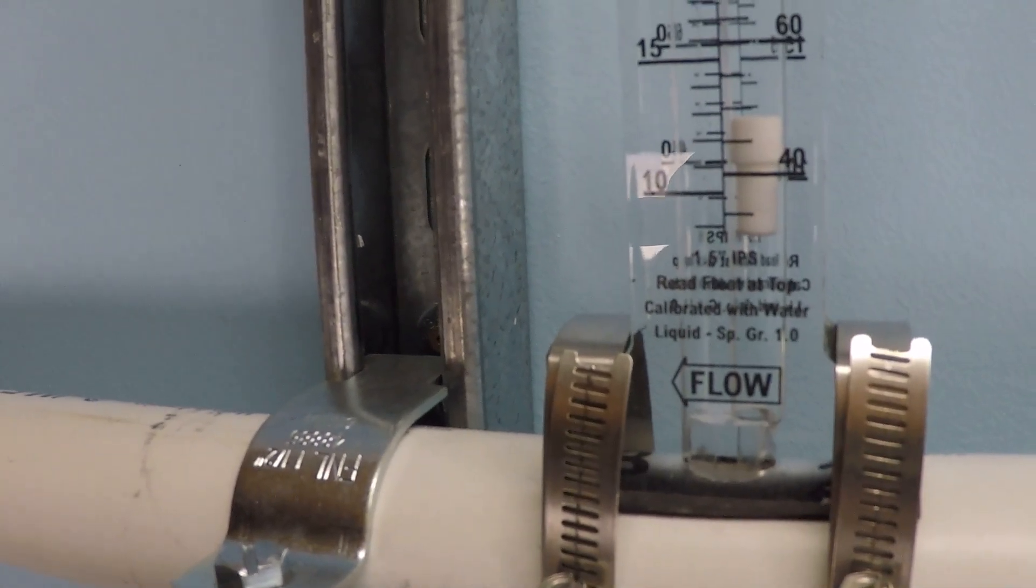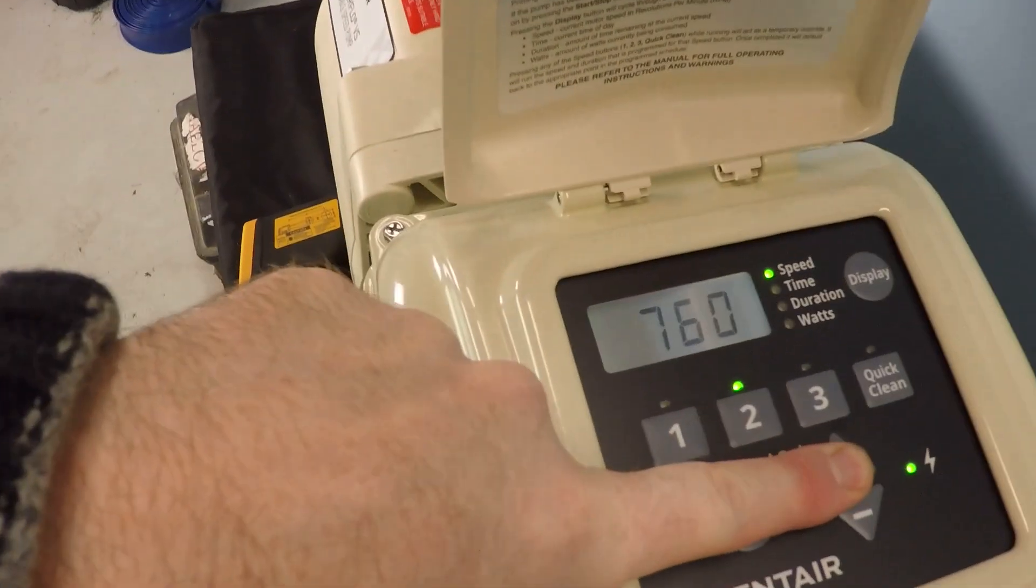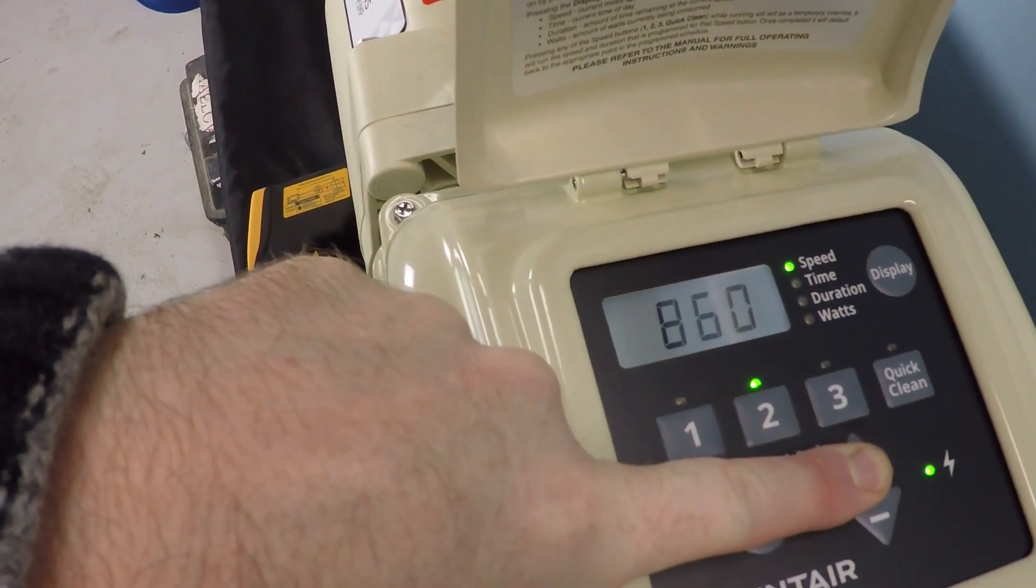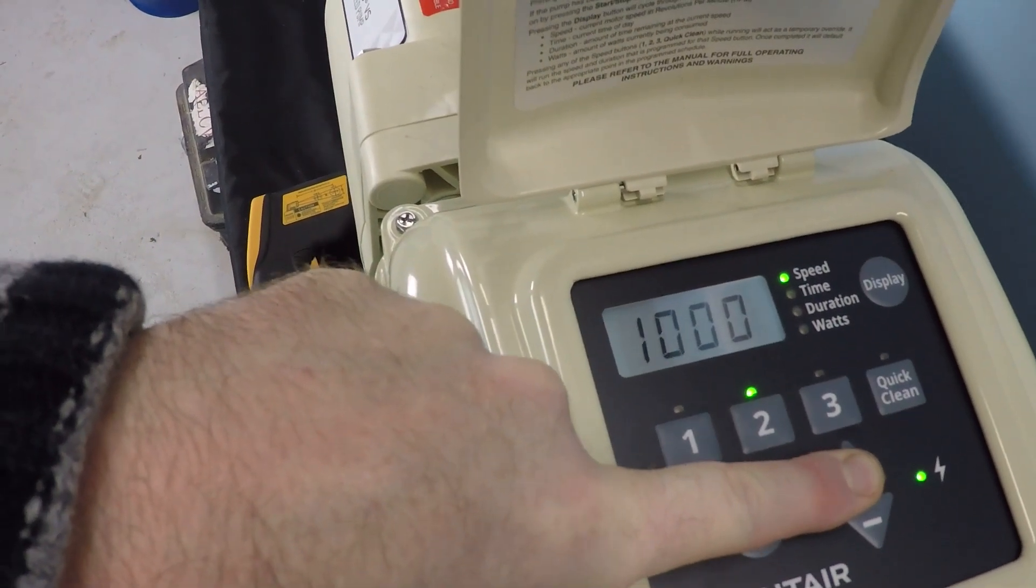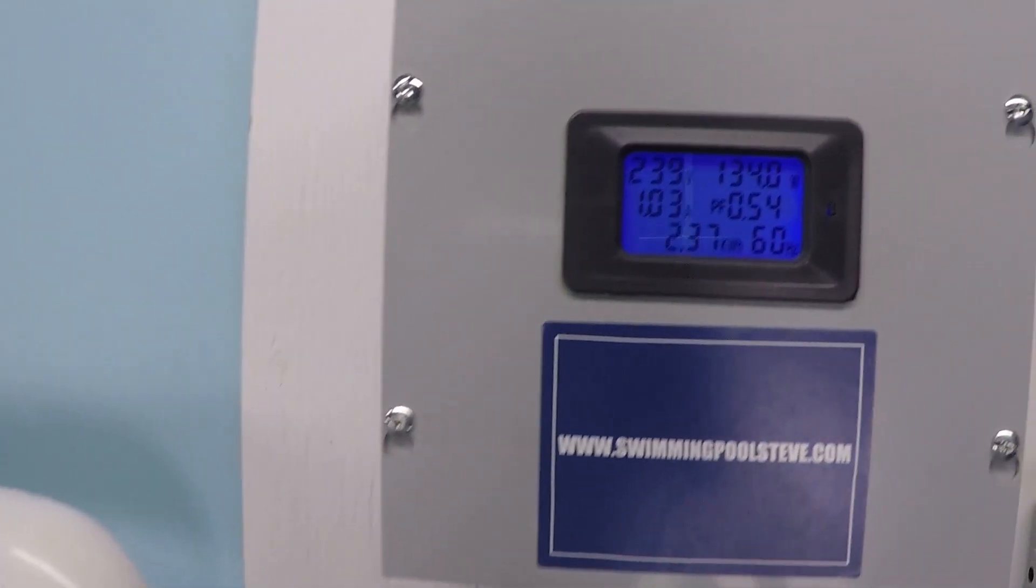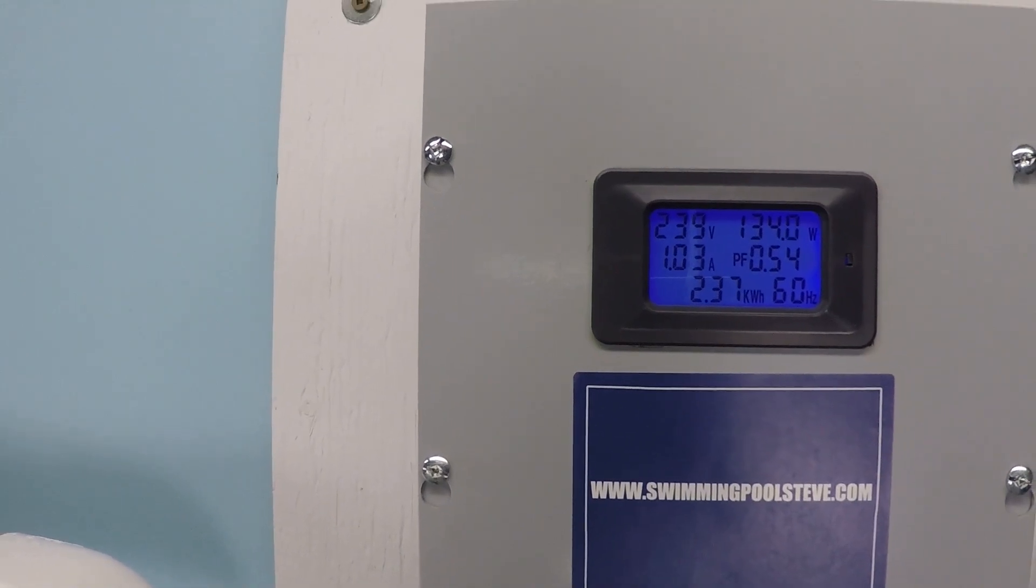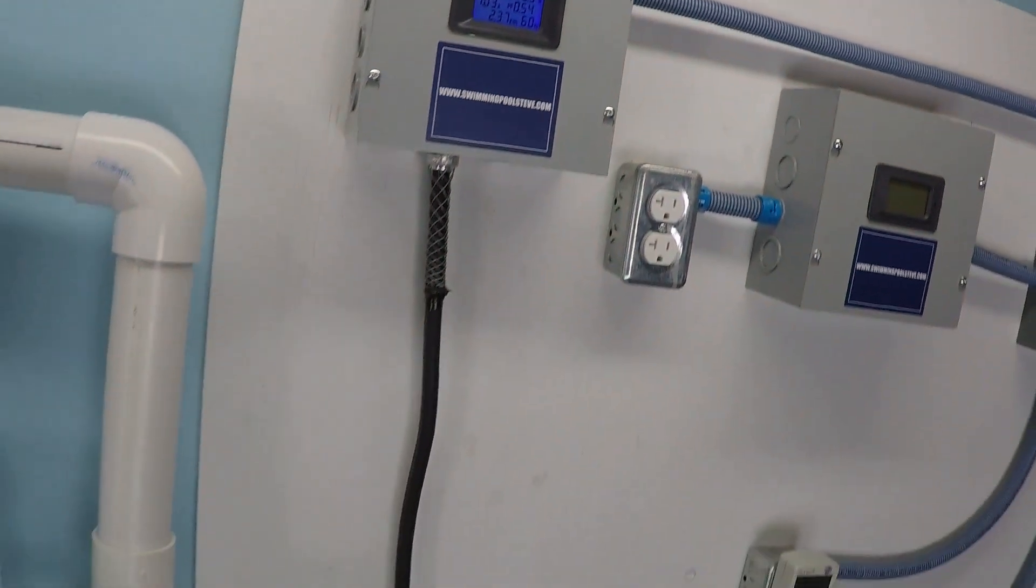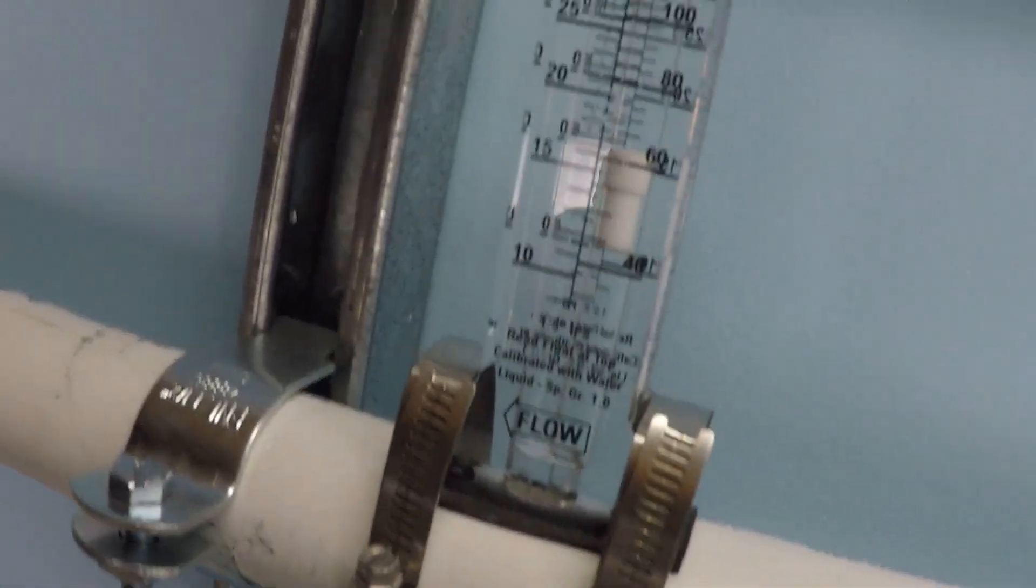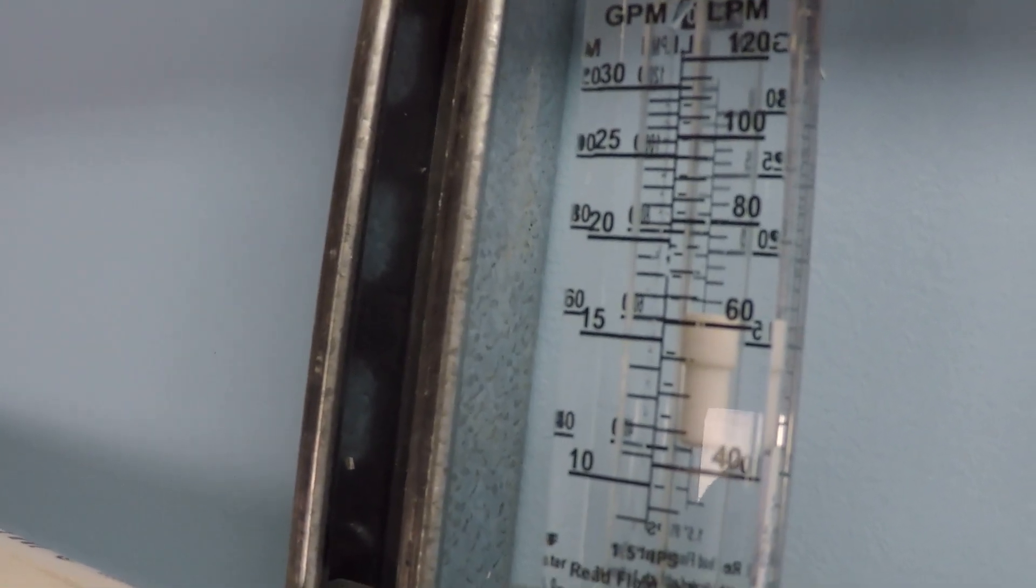1000 RPM, just over 1 amp, 1.03 amps, 134 watts, seeing about 16, 16 and a half gallons per minute.